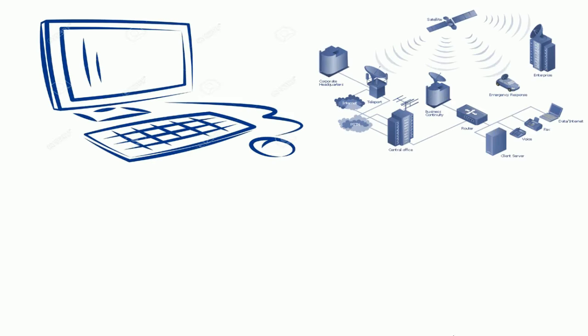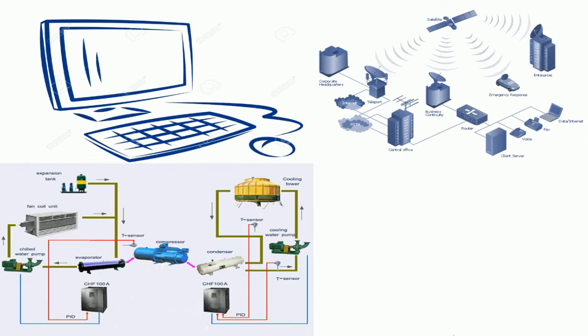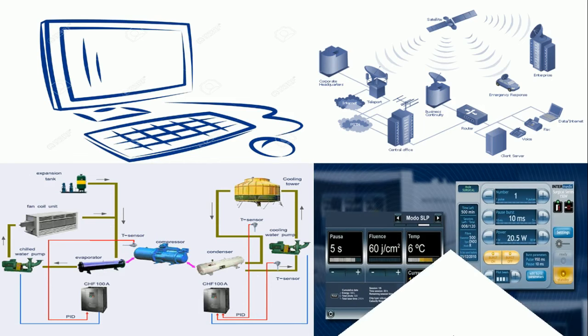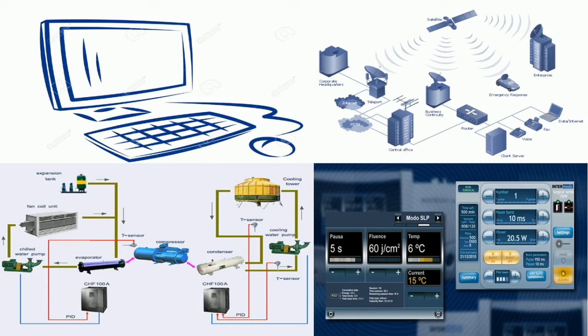The two important elements involved in a modern SCADA system are the RTU and the central station computer. SCADA systems start by communicating in real time with the controllers out in the field that are running the actual process — typically these will be PLCs or RTUs. The SCADA system will gather information from these field controllers. SCADA systems also include some sort of historian product so that real-time process information can be tracked over the long term. It accesses data from PLCs, and after collecting data from the PLC, it is presented on a monitor — it looks like an animation, a virtual display.